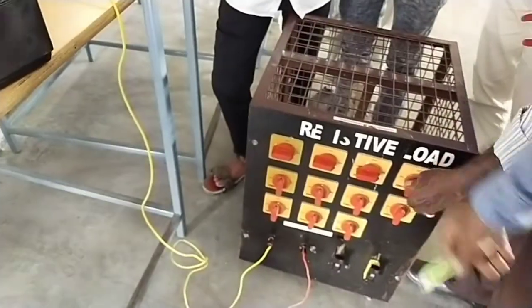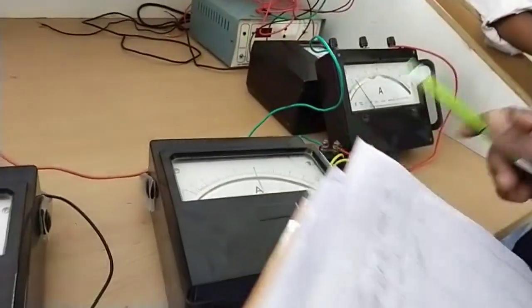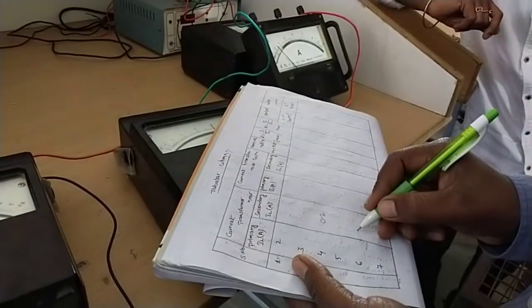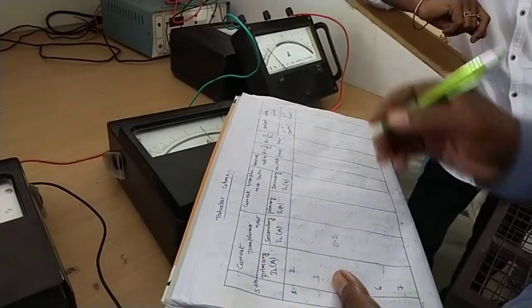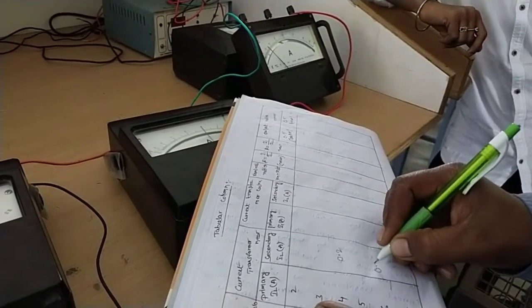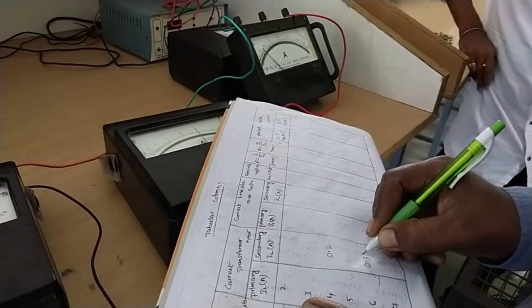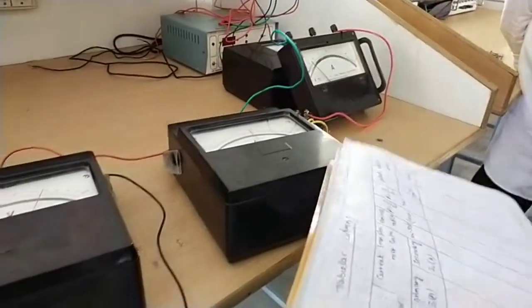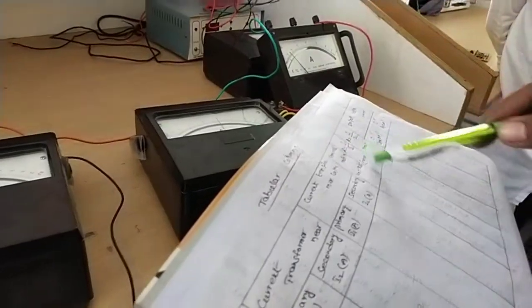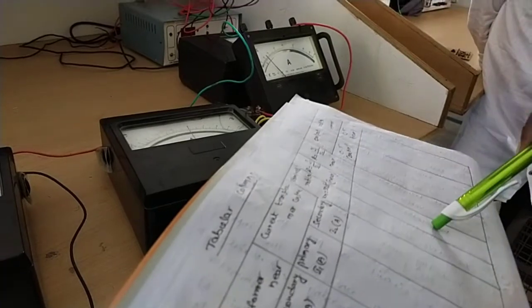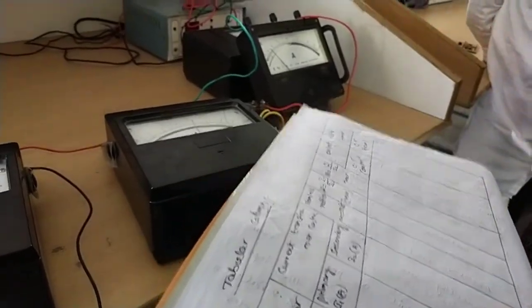Increase the load — the primary current is now 6 amps. The CT secondary reading is approximately 0.3 to 0.35 amps. We are taking many such readings. From these, I1 by I2 gives the transformation ratio R. From the ratio, the ratio error will be calculated using the formula: ratio error = (KN minus R) divided by R, multiplied by 100.